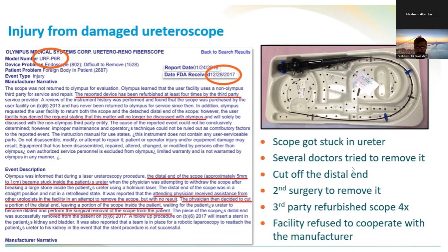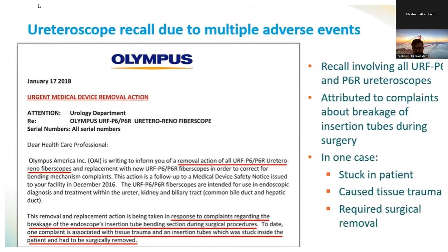Next, you can see that eventually this specific ureteroscope had to be recalled due to multiple events, and it was attributed to the same reason that was mentioned in the report itself. As you can see here, they recalled all the devices involved under this brand name. It was attributed to complaints about breakage of the insertion tube during surgery. In one case, it got stuck in the patient, caused tissue trauma, and required surgical removal, and it's all there. So as you can see, the recall and the FDA were on the same page with the reports that we showed and the results that we had.